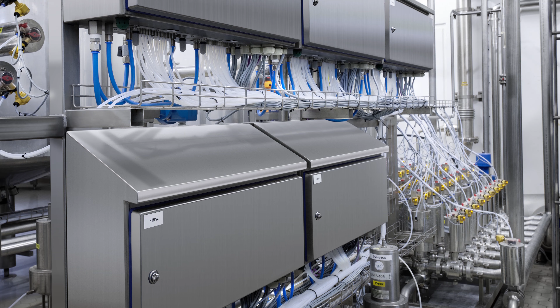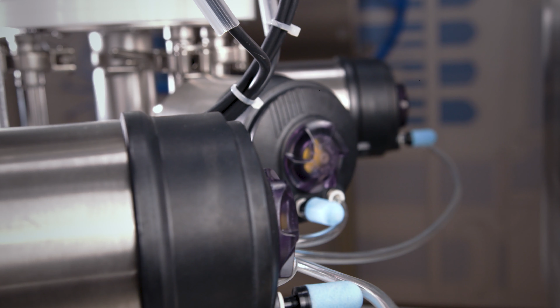The distance between the field device and its control technology leads to long tube and wire lengths, as well as a high number of electric and pneumatic connections. This results in high efforts for wiring and tubing, as well as related tasks such as engineering, documentation, sourcing and commissioning. Things can get much easier using decentralized automation combined with direct digital connectivity on the field device.